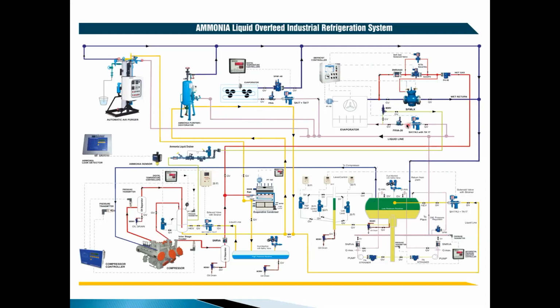And then you see this is a typical evaporator, as I was talking about, with a hot gas defrosting arrangement. So we have a liquid feed solenoid valve. We have here a flow regulating valve. Now what happens is, it is all in the pump vessel, we already have an expanded liquid. So the liquid which is coming from the pump is expanded liquid, at a little higher pressure. So you cannot use a normal expansion valve here because normal expansion valves are designed for a high pressure drop. So you have to use a very special control valve which will generate a very small pressure drop, depending on the pump pressure and the pressure drop across the evaporator. So here you have specialized flow control valves.